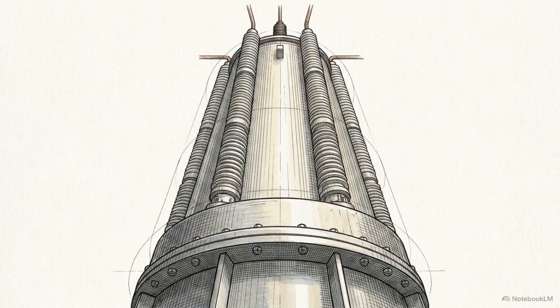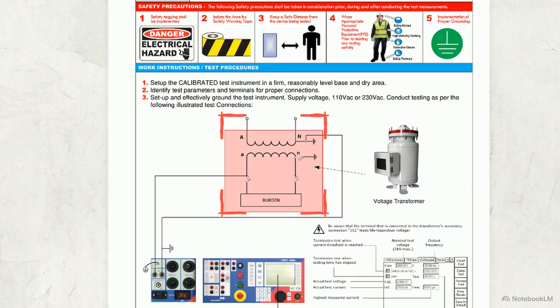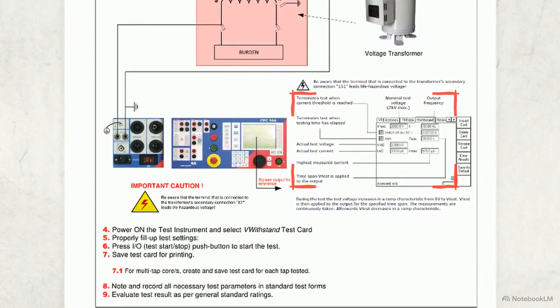The final major hurdle is the high-voltage withstand test. This diagnostic pushes the dielectric boundaries we verified earlier to their absolute operational limits. This connection diagram shows the withstand configuration, where operators short the winding connections and prepare to apply up to 2 kilovolts of alternating current across the target boundary. The application is tightly controlled. The voltage follows a specific ramp characteristic, rising slowly from 0 to the target limit, holding for the measurement span, and then steadily ramping back down.